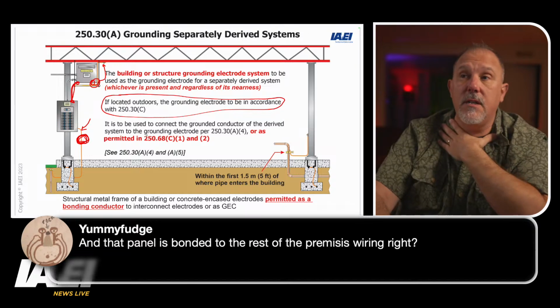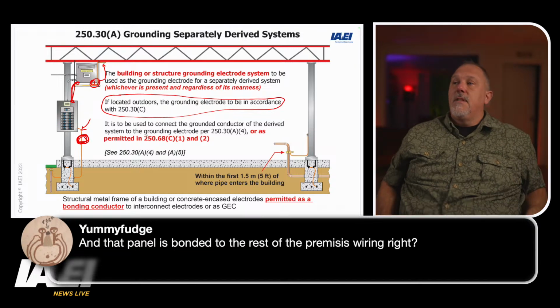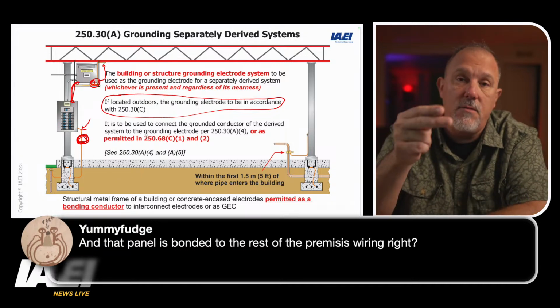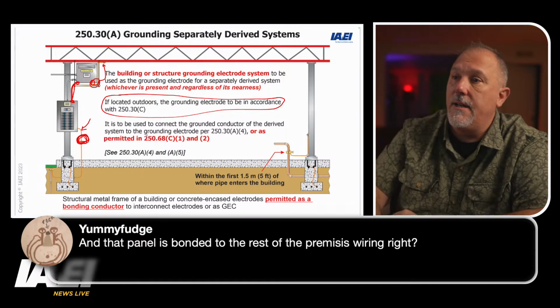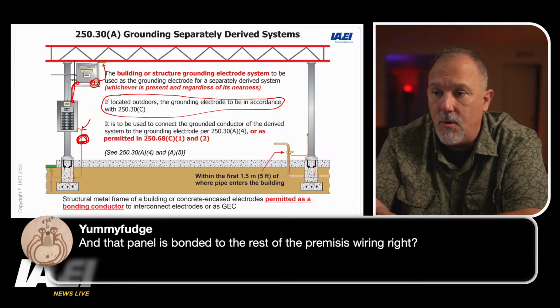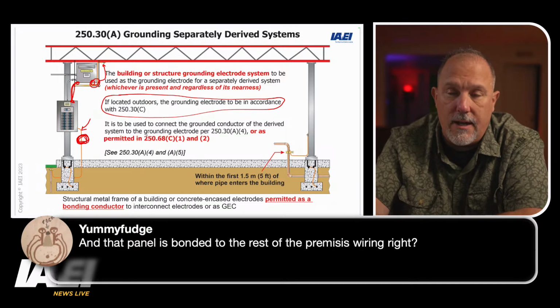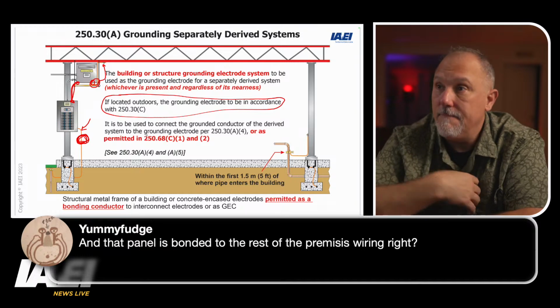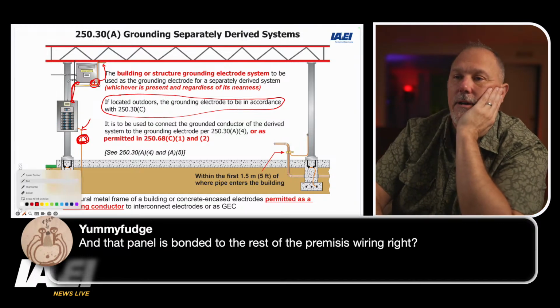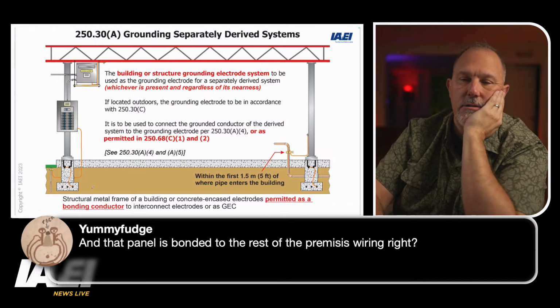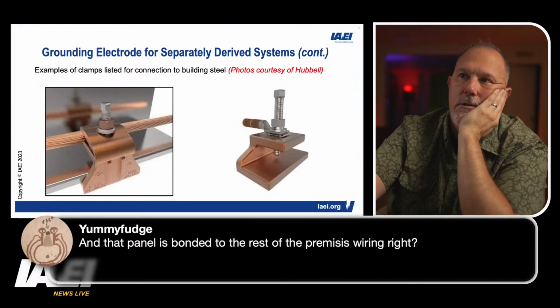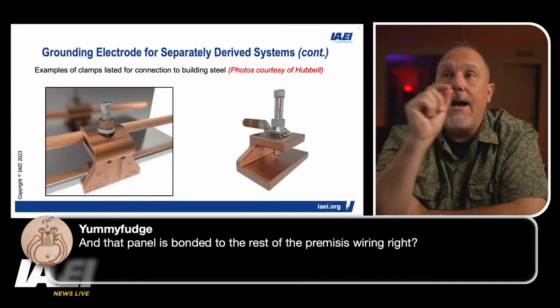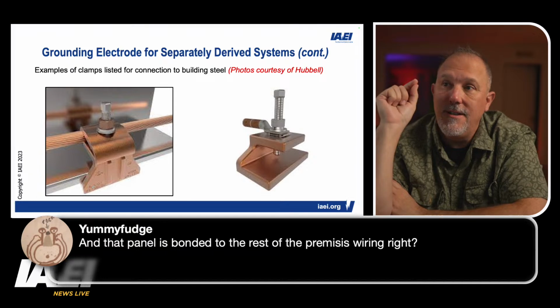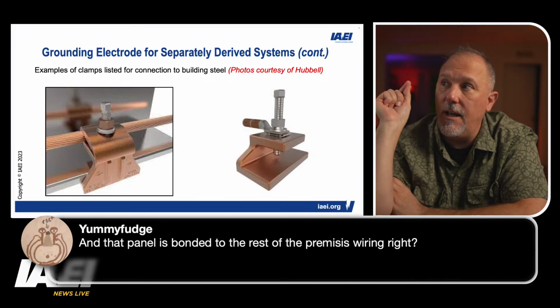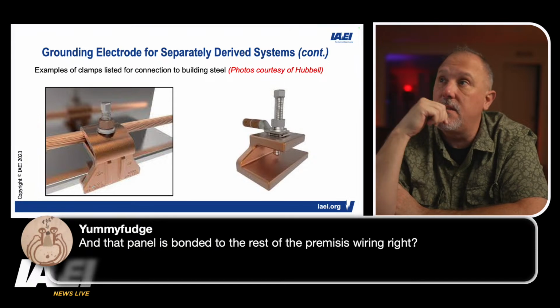Personally, I would have done this in 2 slides. That's the challenge when you're trying to give 2 messages in 1 slide. It's hard to read the slide. You need a guy like Don Gannier or Steve or one of you guys to explain it to me. In any case, I don't like multiple messages on 1 slide. How we connect the grounding electrode is critical, and it's important that we do it correctly and we use listed equipment.